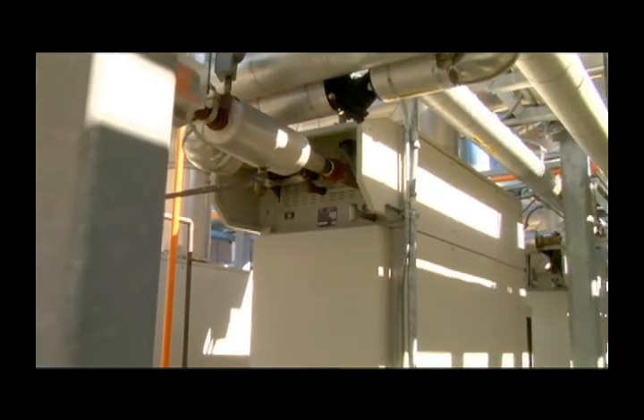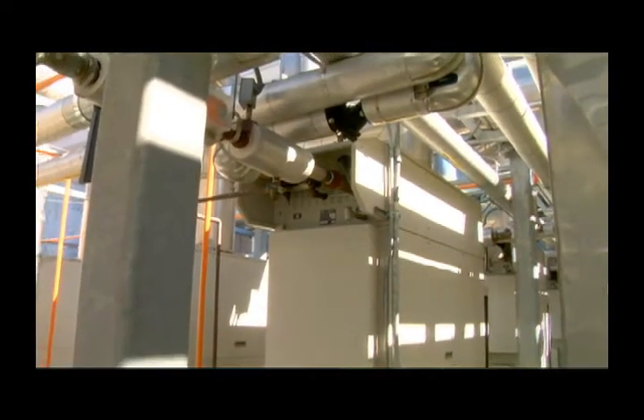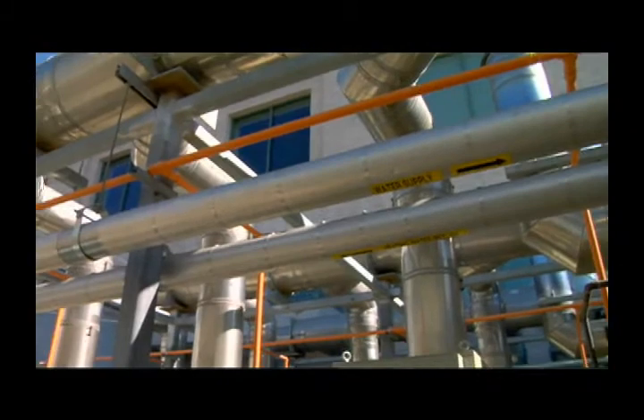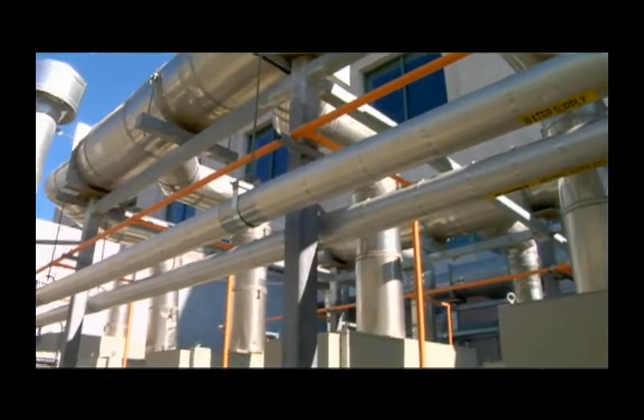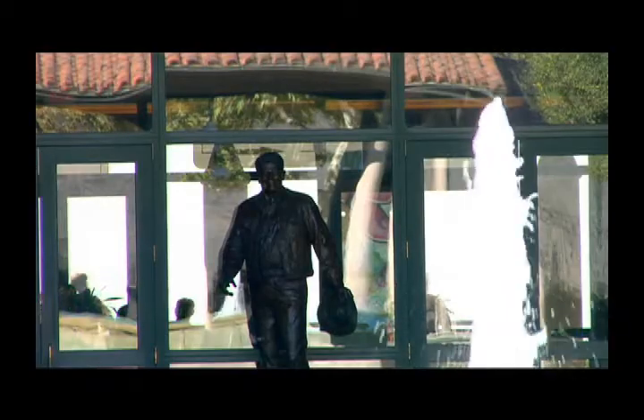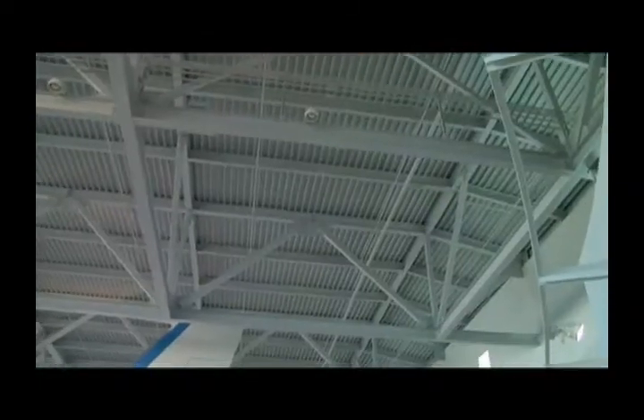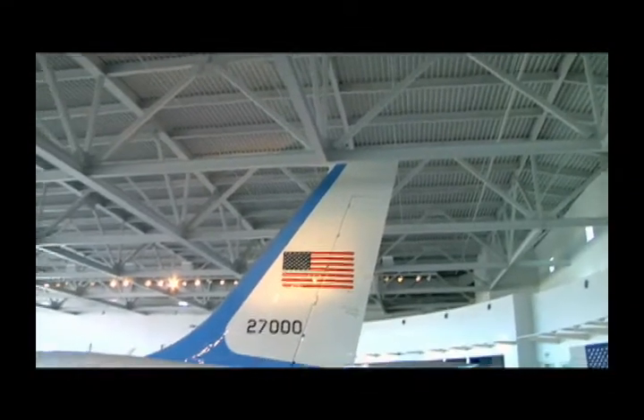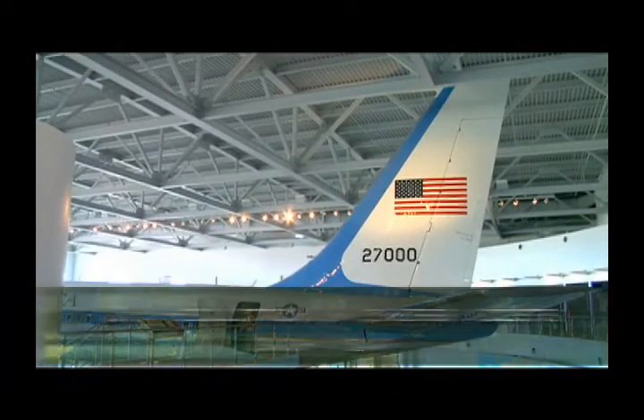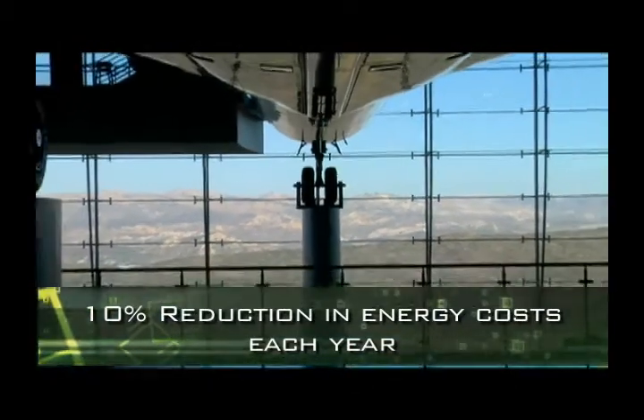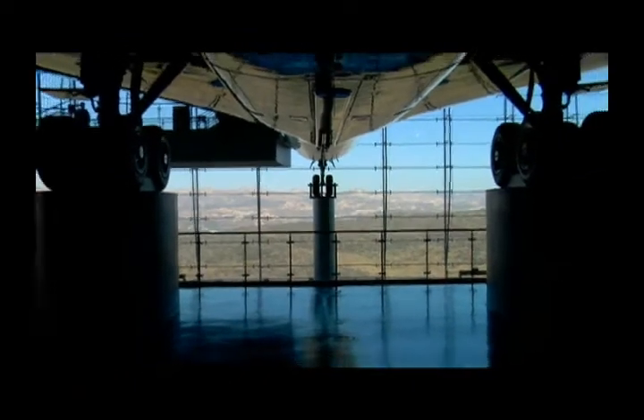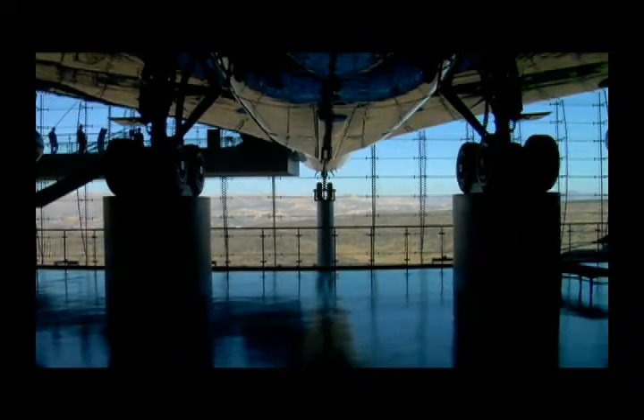prior to going into the chiller, and that heats the hot water, which gives us the heating capability for our building as well. All three of those, the hot water, the cold water, and the electricity, all come out of this one plant and provide the entire campus with chilled water and electricity, in a very efficient package. The Capstone microturbines also have reduced Reagan Library's energy costs about 10% on average each year. Just one more reason the library is pleased with the installation.